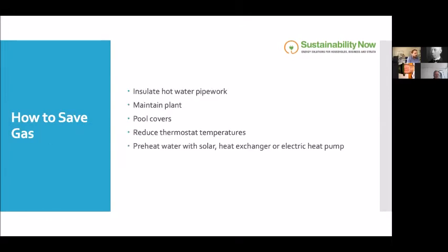So gas, we see quite a lot of domestic hot water systems, large commercial domestic hot water systems with uninsulated pipework. So essentially those hot water systems are just acting like a cooling tower. They're pumping water around a network of pipes that is uninsulated, and it's just expelling its heat to the atmosphere. So that's a waste of gas. So making sure that your hot water pipe work is well insulated, and that goes for some of your hot water condenser water pipe as well.